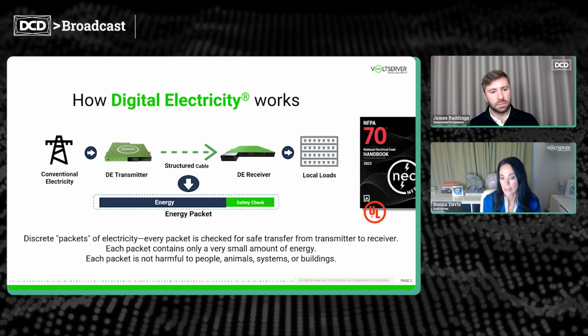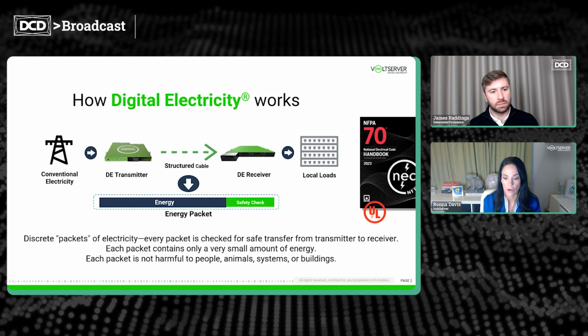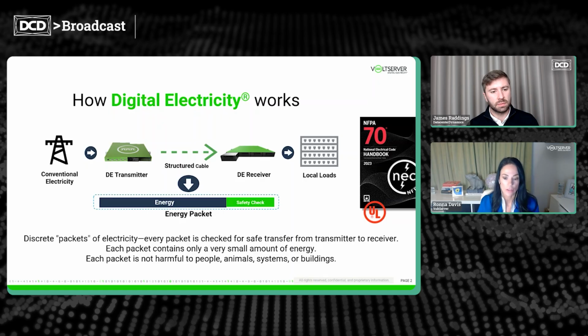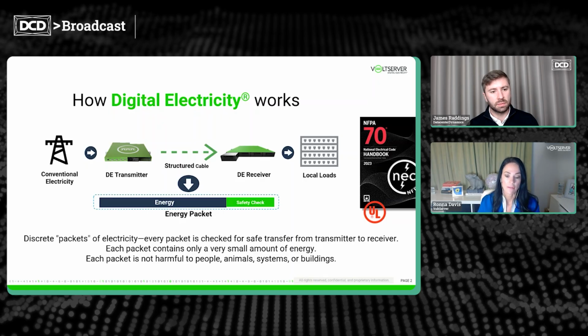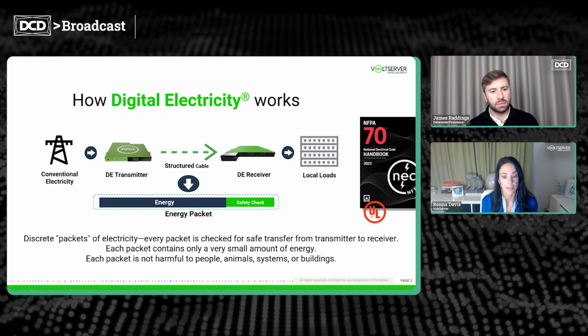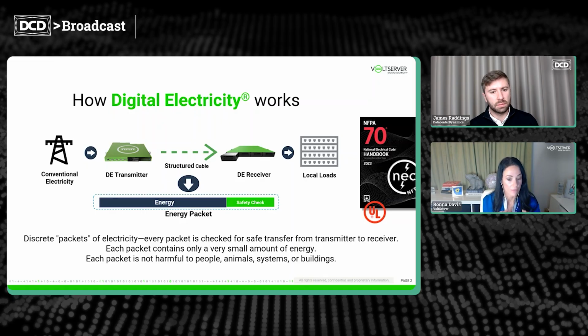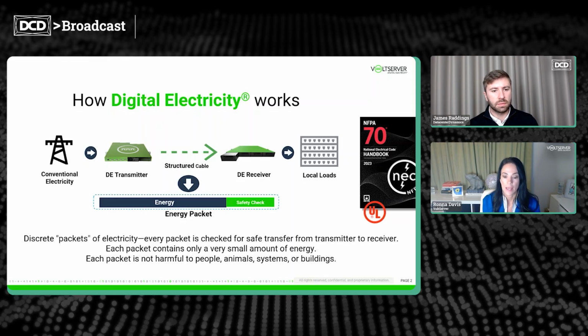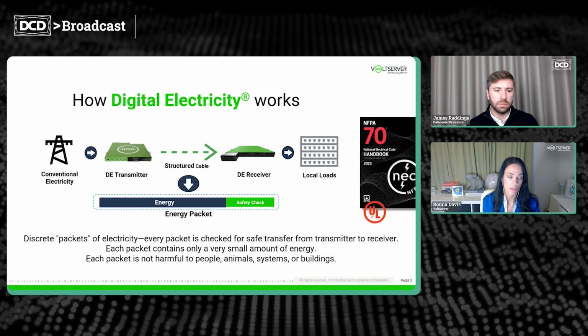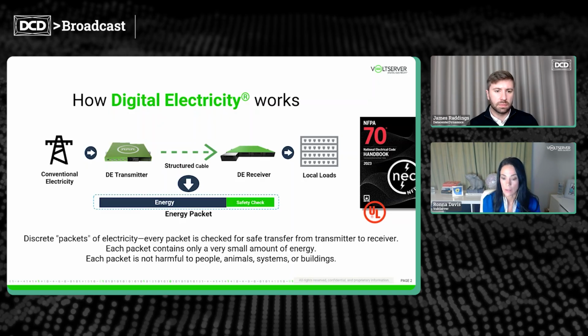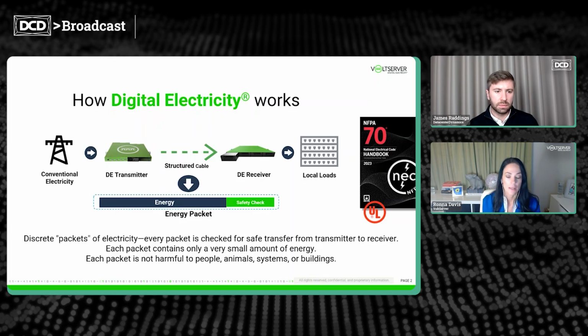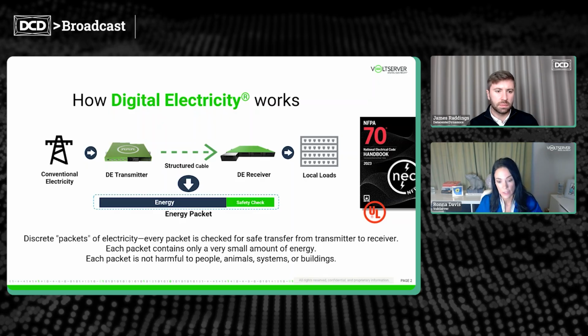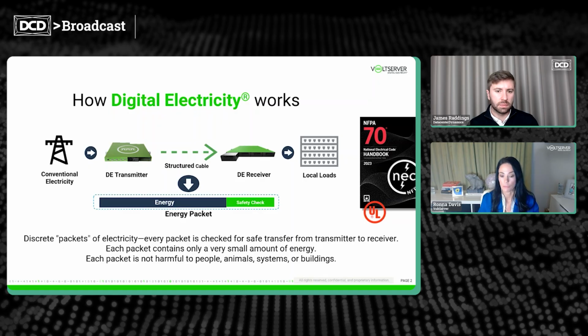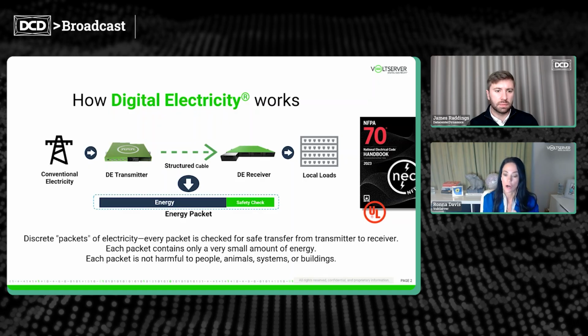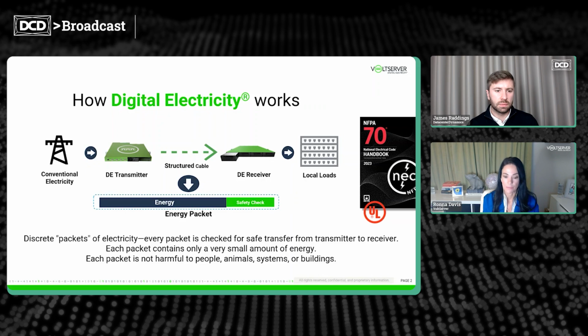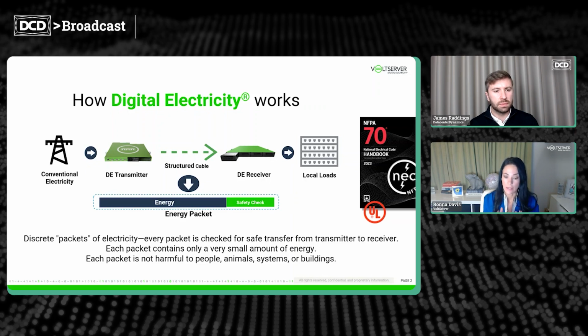Each one of our energy packets includes data for a safety check on the line. We are constantly monitoring the line for any fault or decay, and if a fault is detected, we don't send the next packet of energy. This happens very quickly, in under 4 milliseconds, and it limits the amount of energy into the fault to such a level that it will not cause electrocution or fire. This is what makes our technology safe to interact with and eliminates the need for breakers, arc flash protections, conduits, and lockout-tagout areas. Our transmitter is a solid-state transformer.